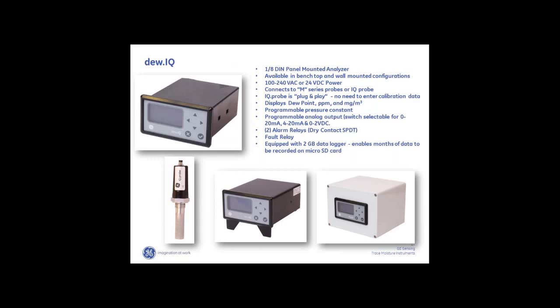The calibration data is stored in the probe and automatically uploaded when powered. You can stock a spare probe and rotate them in and out of service — with smart probes there's no possibility of entering the wrong calibration data. The unit also has relay outputs that can be set to alarm at preset values. Some customers use those relays to engage a heating cycle, a regeneration cycle, or turn on a purge gas when things get too wet. In addition to the relays, there is a programmable linear 4 to 20 milliamp analog output and a two-gigabyte data logger.